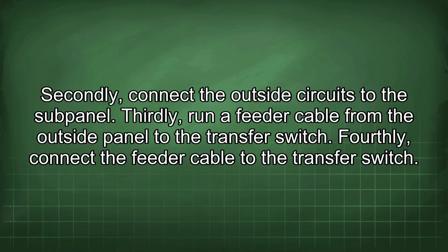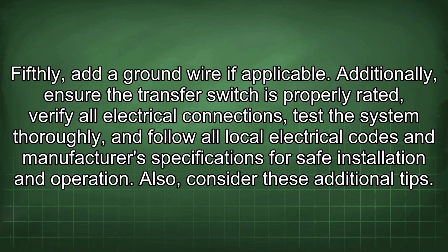Thirdly, run a feeder cable from the outside panel to the transfer switch. Fourthly, connect the feeder cable to the transfer switch. Fifthly, add a ground wire if applicable. Additionally, ensure the transfer switch is properly rated, verify all electrical connections, test the system thoroughly, and follow all local electrical codes and manufacturer's specifications for safe installation and operation.